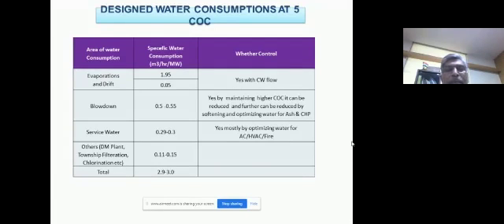So that is the belief we have, and therefore we are taking the drift and evaporation loss per hour per megawatt, the blowdown, the service water, and other DM, township, filtration and chlorination, and in total it is going to 2.9 to 3. And here I would like to emphasize that the recent notification which has come from the CPCB gives the water utilization as 3.5 meter cube per hour per megawatt. But our design is still quite conservative, from 2.9 to 3.